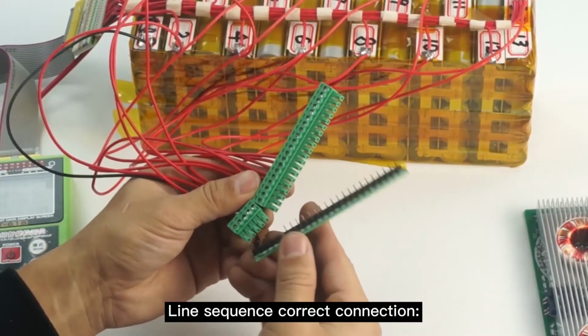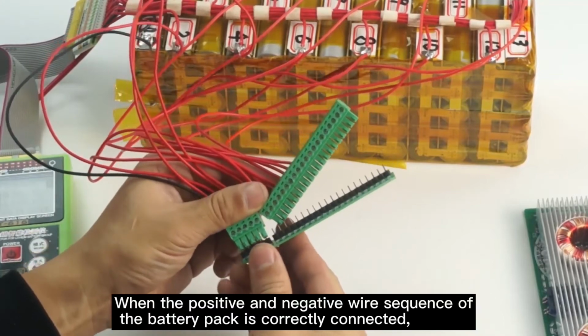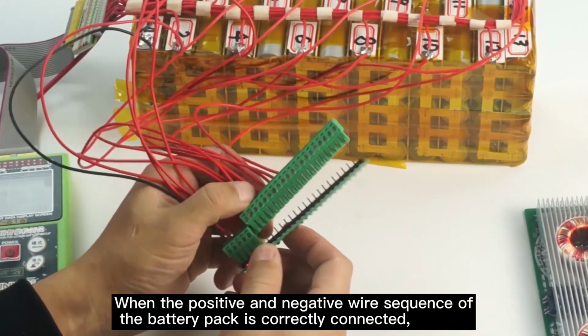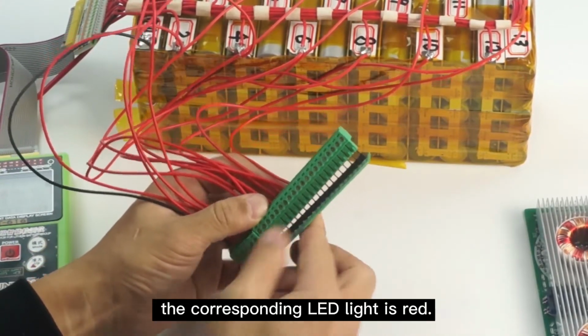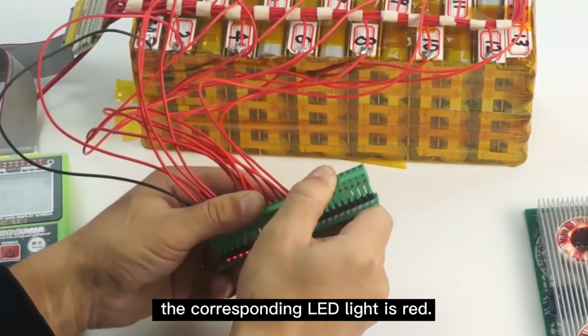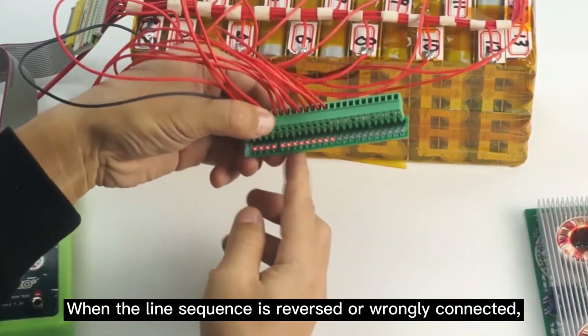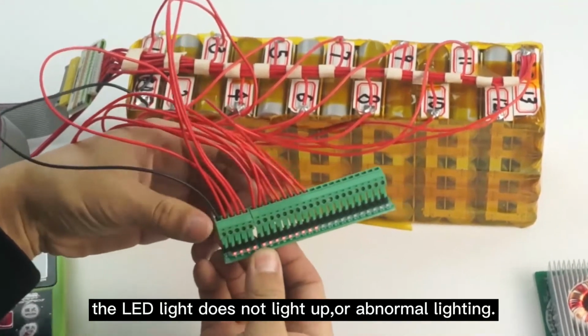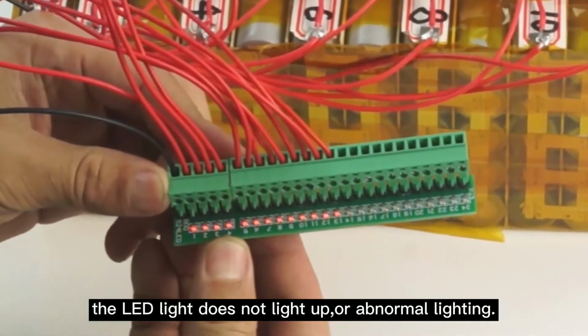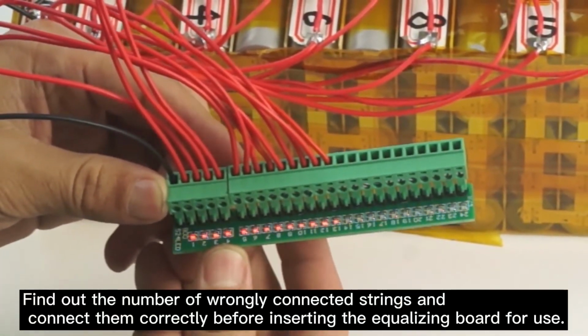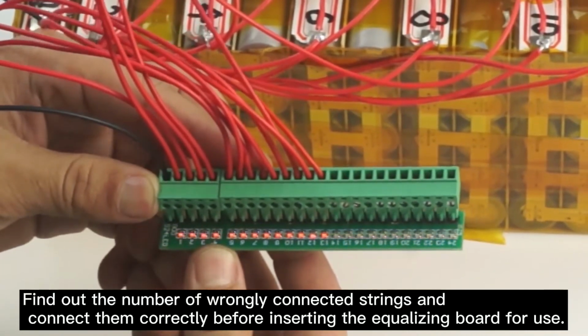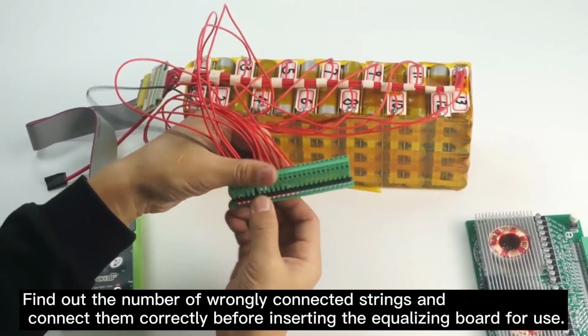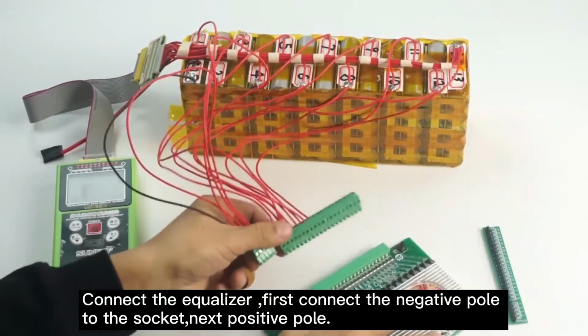Line sequence correct connection. When the positive and negative wire sequence of the battery pack is correctly connected, the corresponding LED light is red. When the line sequence is reversed or wrongly connected, the LED light does not light up or lights abnormally. Find out the number of wrongly connected strings and connect them correctly before inserting the equalizing board for use. Connect the equalizer.